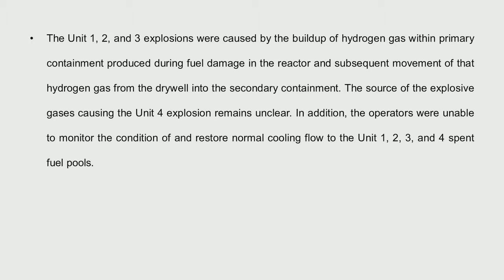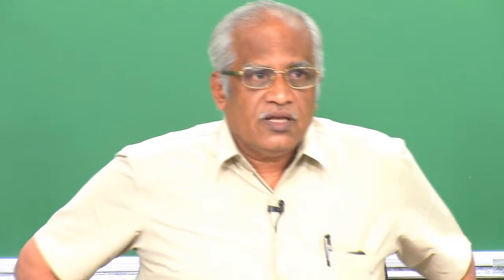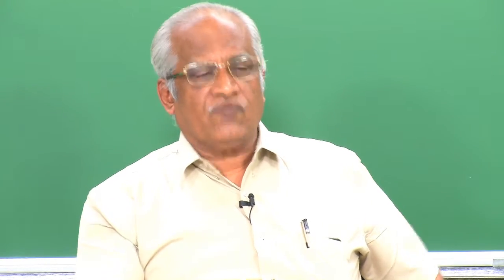When this accident happened, normally we review all our reactors whether such things can happen. We looked at our own facilities near the sea. We looked at the Kudankulam power plant — we had already placed the diesel generators at about 15 to 20 meters height from sea level. So with those margins built in, we concluded that such an accident cannot happen. However, we did have a tsunami in 2004 during which there was a flooding of the Kalpakkam plant, which we shall see later — though nothing happened.